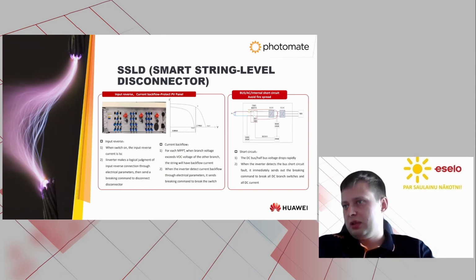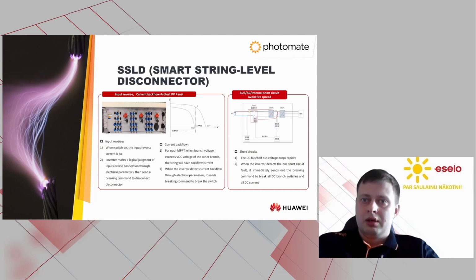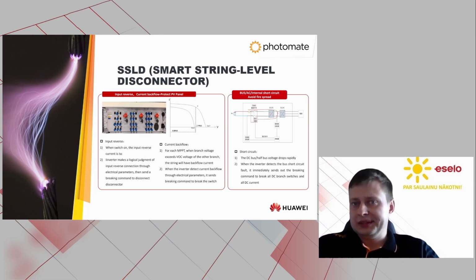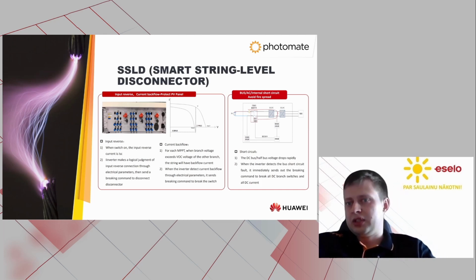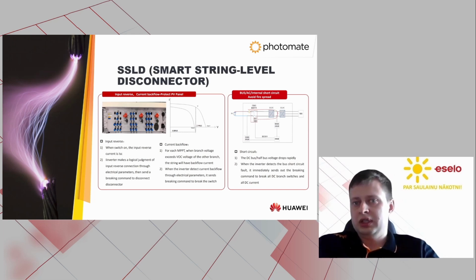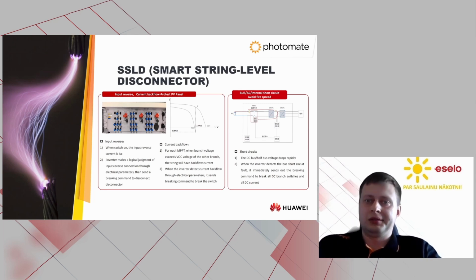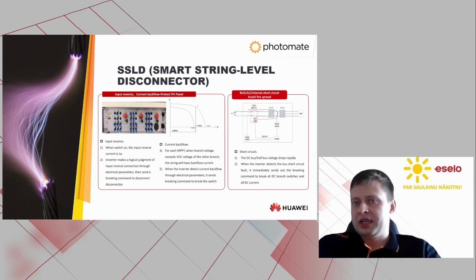About the new inverter, which is going to be released soon, the 330 kilowatt inverter. It has a very good advantage, which is called SSLD. What does it mean? It's the smart string level disconnector. This disconnector is an electrically controlled switch designed to protect against 3 different types of faults. The first fault is reverse input current, which occurs when the switch is on and the reverse current is equal to the short circuit of the string. In this case, the inverter makes a logical judgment based on the measured parameters and switches off the circuit to prevent damage.